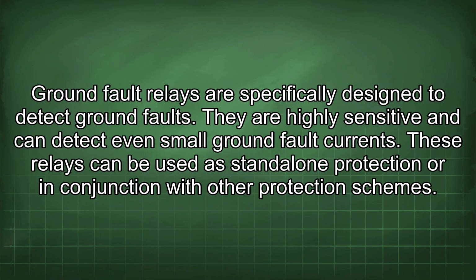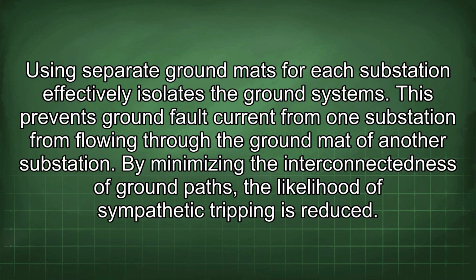Ground fault relays are specifically designed to detect ground faults. They are highly sensitive and can detect even small ground fault currents. These relays can be used as standalone protection or in conjunction with other protection schemes. Using separate ground mats for each substation effectively isolates the ground systems. This prevents ground fault current from one substation from flowing through the ground mat of another substation. By minimizing the interconnectedness of ground paths, the likelihood of sympathetic tripping is reduced.